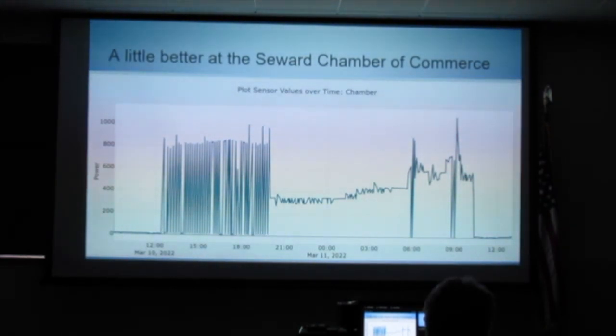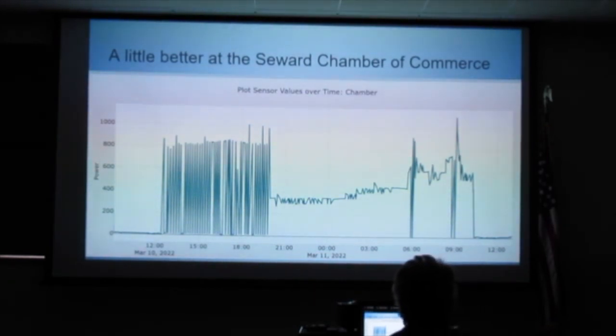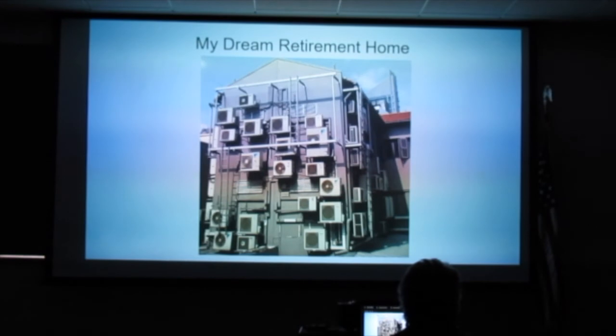They got a little bit more smarts, I guess, and I don't know exactly what the issue is. Is it just their expansion valve? I think their outdoor unit's pretty dirty. Do some maintenance down there, get an air compressor and blow it out, clean it out a little bit. We'll get into maintenance, yeah. I've been down there a few times and checked those filters on the indoor unit, and they're caked full of dust, which really doesn't help anything. So you've got to check those filters.